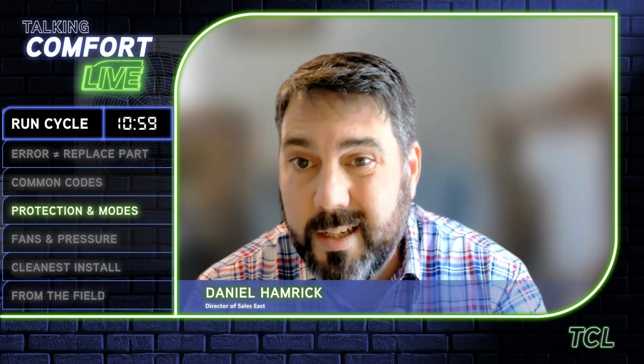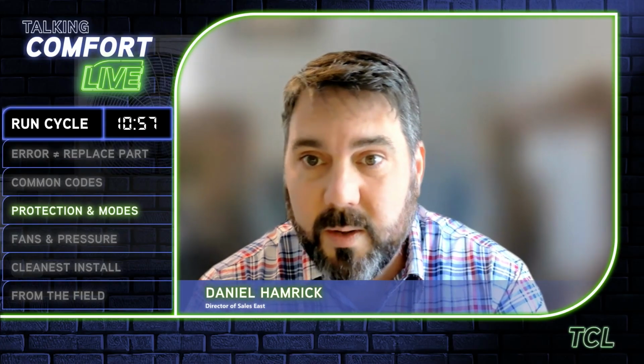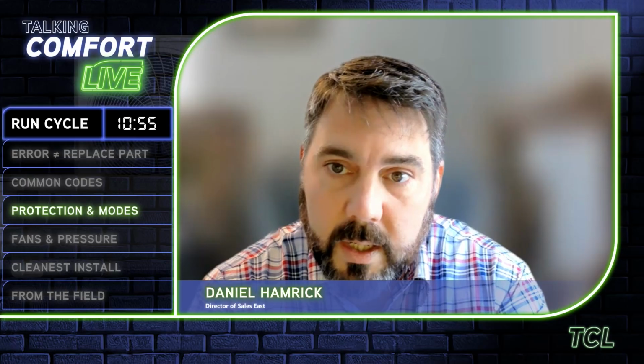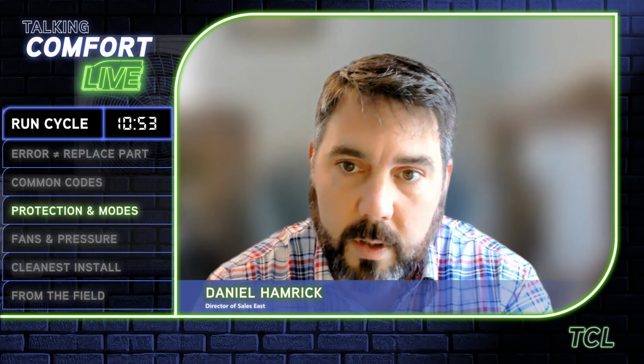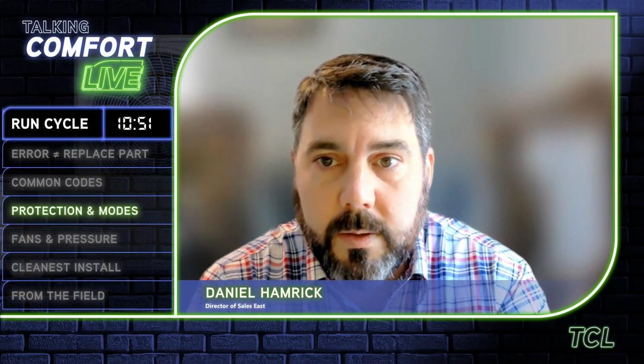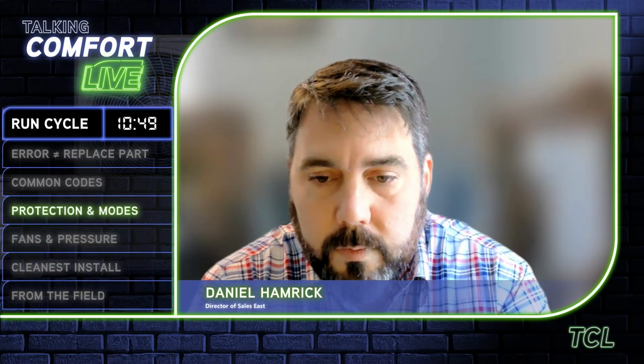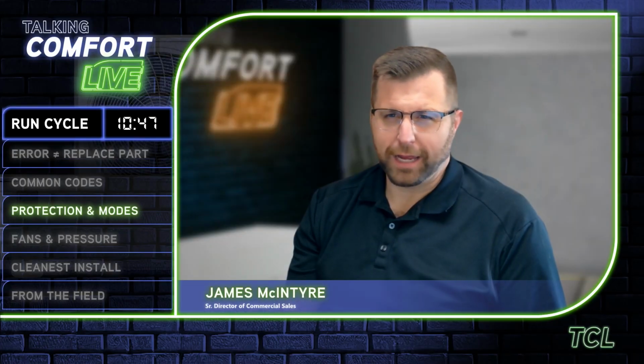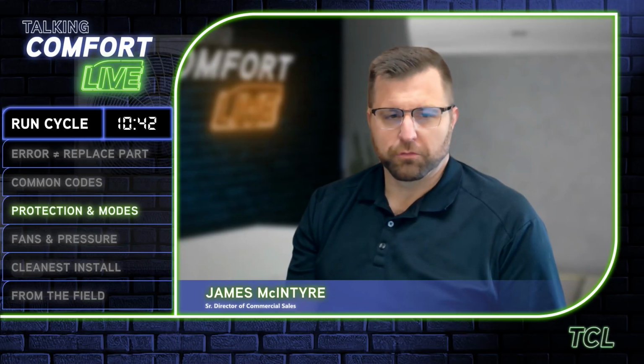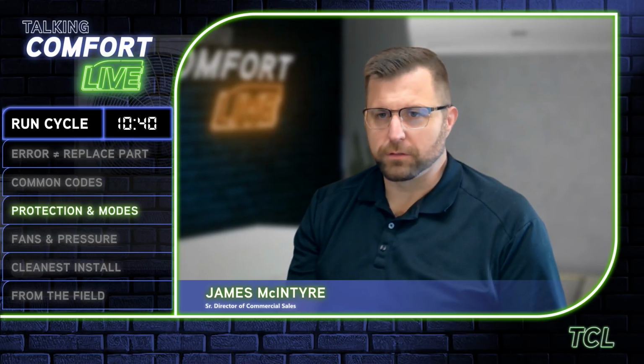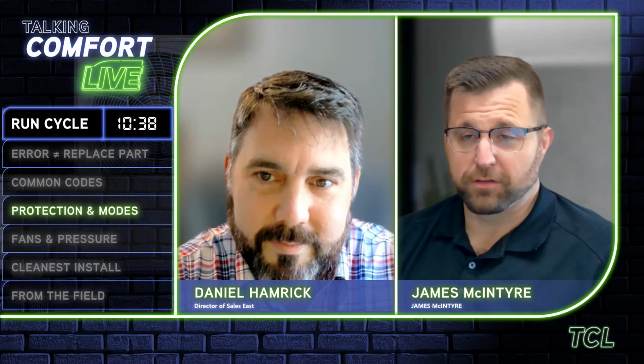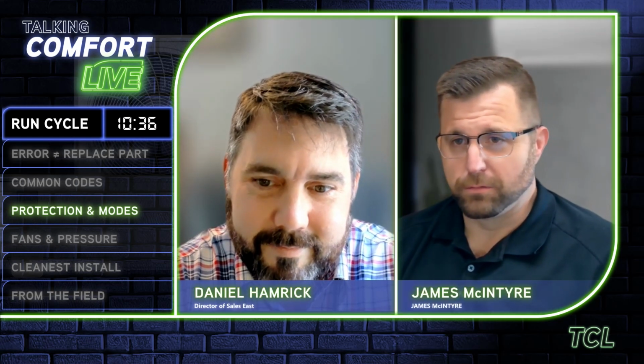Even if it didn't get to the point where it was like, hey, I can't expel this heat, I got to throw an H4, it's still often doing that oil return to get oil back to the compressor. So you're saying because of low airflow, I'm running at a low capacity condition for an extended period of time, right? Yes. So you tricked it into running at a lower capacity, right? I mean, I guess dehumidification is probably great.